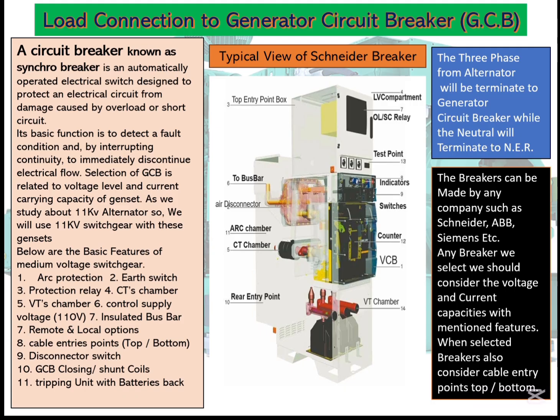This is a typical view where we have our load cables from the alternator to the breaker. On one side of the breaker, we install our 3-phase cable, and the upper side is the bus bar. From that bus bar, if we have multiple gensets, we install multiple breakers. Then we have outgoing breakers where the customer will install their load cables.